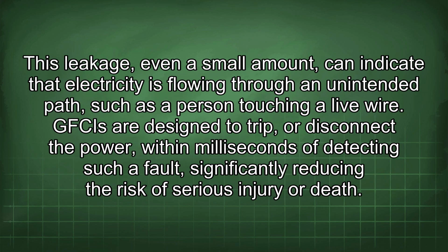This leakage, even a small amount, can indicate that electricity is flowing through an unintended path, such as a person touching a live wire. GFCIs are designed to trip or disconnect the power within milliseconds of detecting such a fault, significantly reducing the risk of serious injury or death.